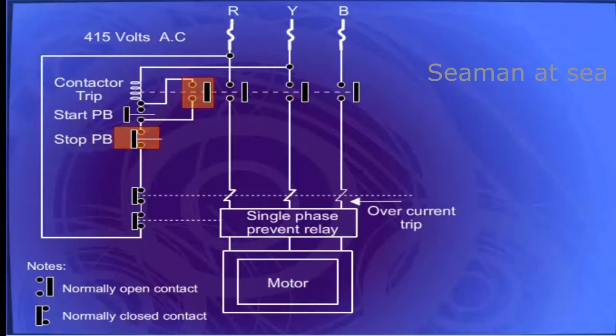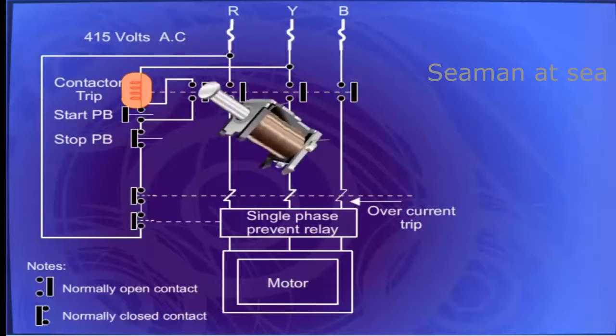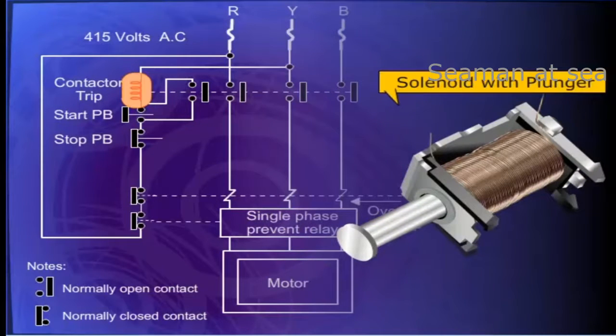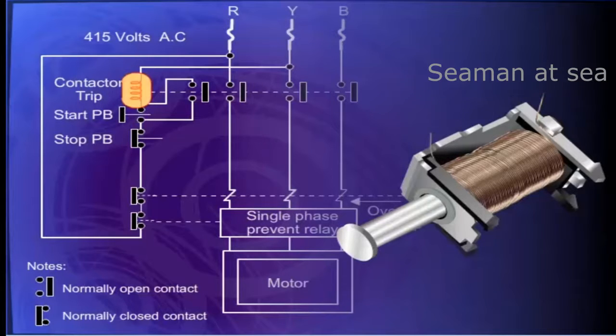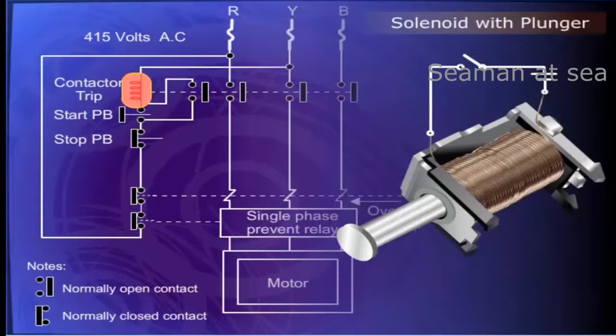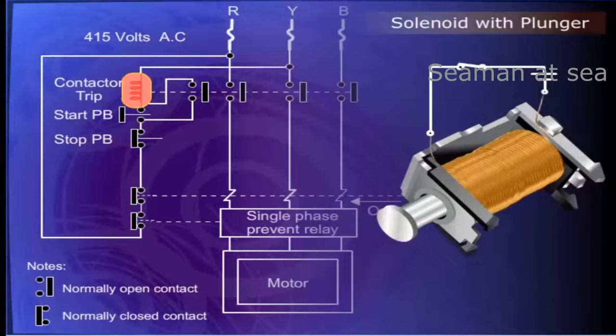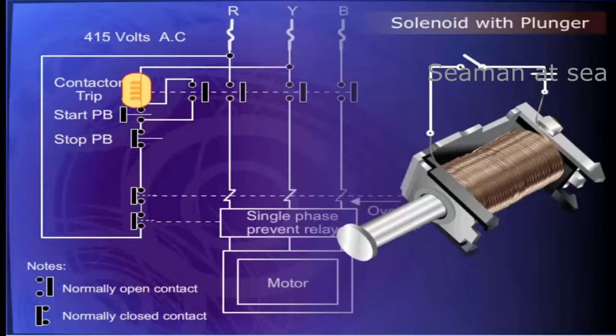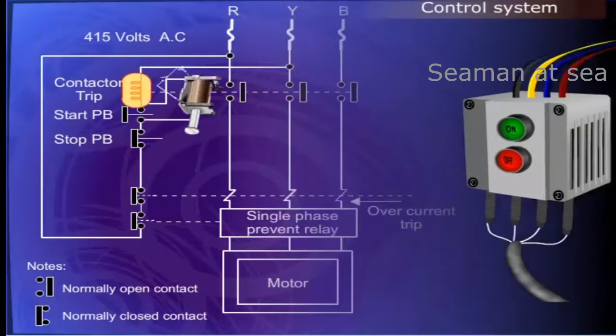Electrical contactor has a solenoid with plunger which moves a set of electrical contacts from closed position to open position or vice versa. The plunger picks up when there is energization of the electromagnetic coil. When the coil is de-energized, the plunger returns to its original position due to spring action.